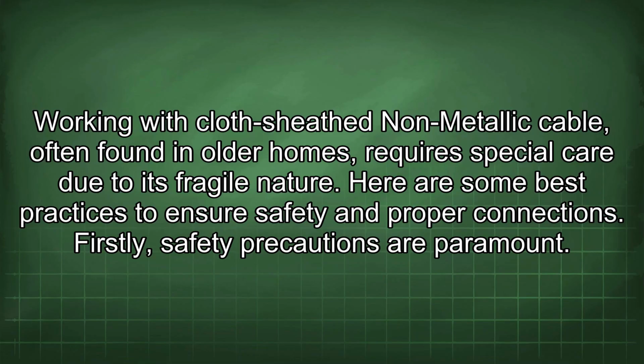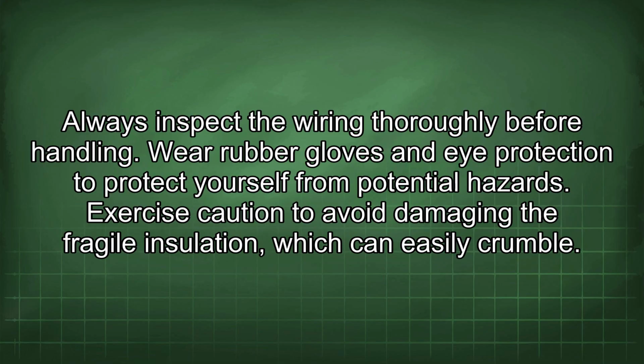Working with cloth-sheathed non-metallic cable, often found in older homes, requires special care due to its fragile nature. Here are some best practices to ensure safety and proper connections. Firstly, safety precautions are paramount. Always inspect the wiring thoroughly before handling. Wear rubber gloves and eye protection to protect yourself from potential hazards. Exercise caution to avoid damaging the fragile insulation, which can easily crumble.